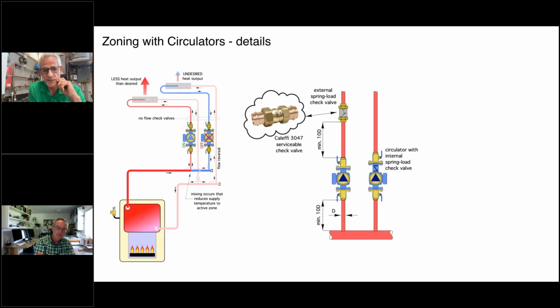They just rattle their brains out eventually. Now, if you can see behind me, I've got that clear glass pipe. I actually put a pump next to that with the check valve, so I could look in there and actually see the check. And I put a video of that on the Plumbing Perspectives site. It shows that even in a good air-free system, that check is always chattering around. And as you change the pump speed, you can see the frequency of that little check vibrate.